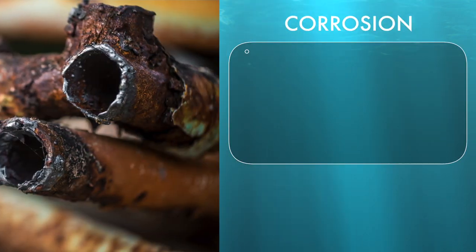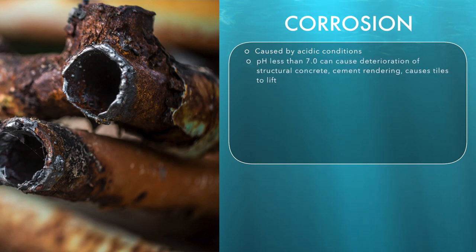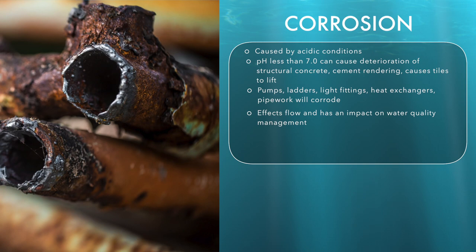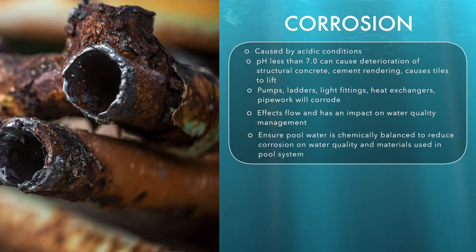Corrosion in pool structures is caused by prevailing acidic conditions, that is, a pH of less than 7.0. Such conditions can cause deterioration of structural concrete, cement rendering, other surfaces and cause tiles to lift. Metal fittings including pumps, ladders, underwater light fittings, heat exchangers and pipework will also corrode. This will affect flow and have an impact on water quality management. It is very important to ensure that the pool water is chemically balanced to reduce the effects of corrosion on pool water quality and the materials used in the pool system.